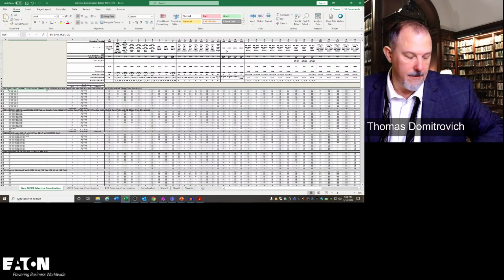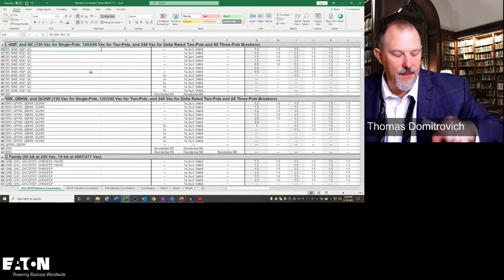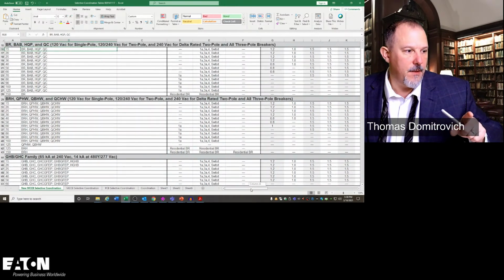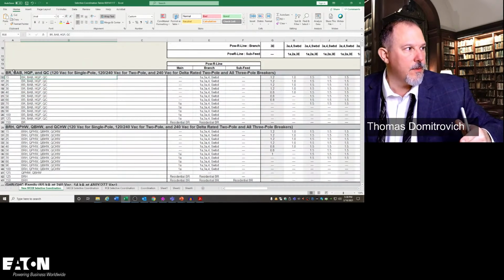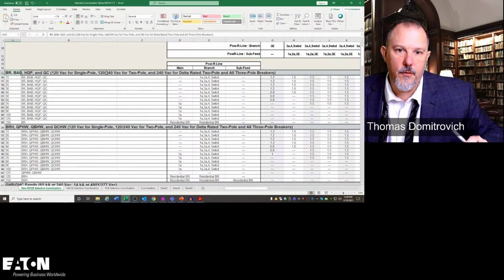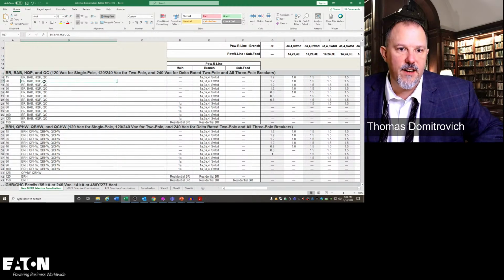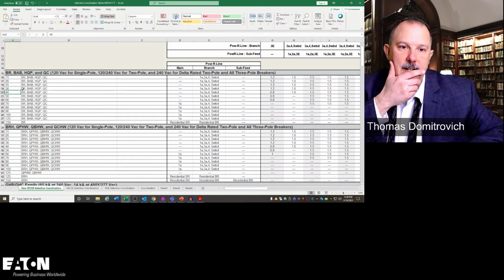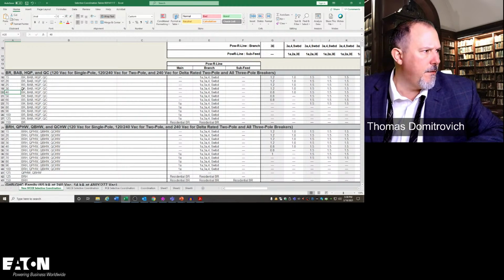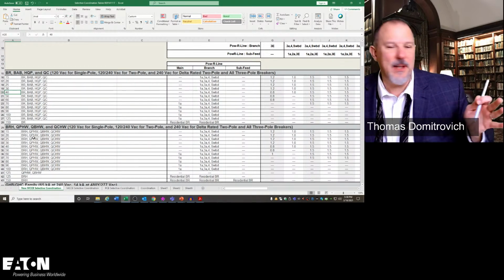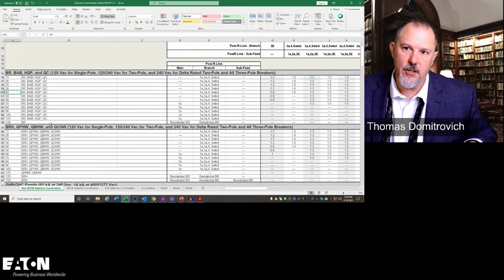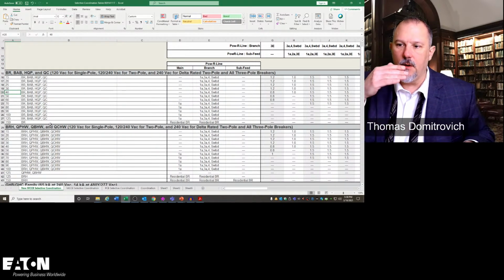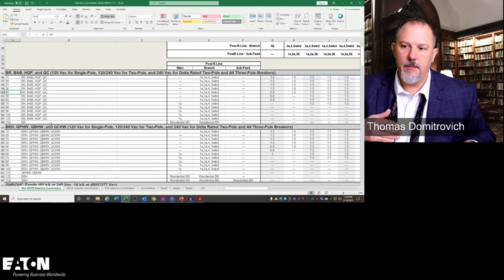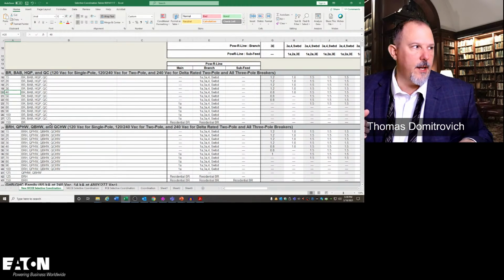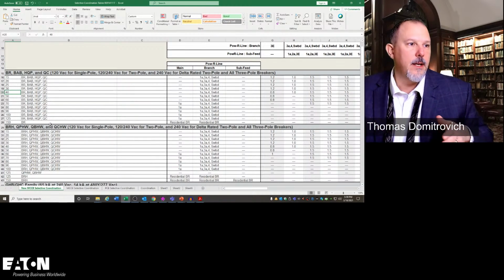I'm just saying. So what I know in this scenario, I have a downstream breaker of a BAB, which is right here. This is a BAB 240 volt, 2-pole and single pole. And look, I have a 15, a 20, 25, 30, 40 on up. And yeah, somebody had commented, what if I go from one to another? In my spreadsheet and our marketing literature on our website, we will jump from one to another, and there are breaker sizes in between. So you always go to the larger.